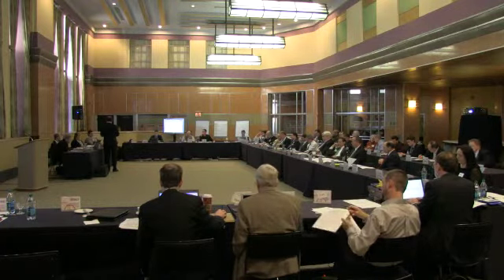Right now, the Museum Center is on a demand-ratcheted schedule, which makes doing an ice storage system financially important for the facility operation-wise. The way that system works is if they go over a certain energy usage, it locks in their rate at a higher rate for a year. By utilizing ice storage and using a lower demand rate at night, they're able to keep their demand schedule down on an annual basis, which helps them leverage their energy rates and keep operating costs reasonable.